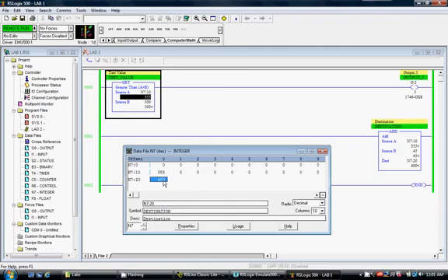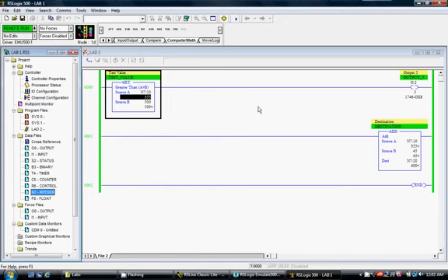That is because this is a result of a calculation, and the 1000 stayed in the data table for one scan. Once it got back to this add instruction, N7:20 was rewritten by the add instruction to be 400. So that's proper. Because this is an unconditional statement, there's no way I can make that change. So that's it. That concludes this presentation on compare and math functions.